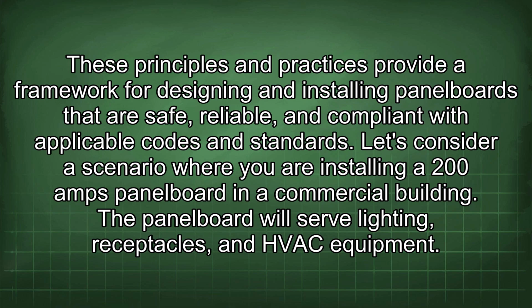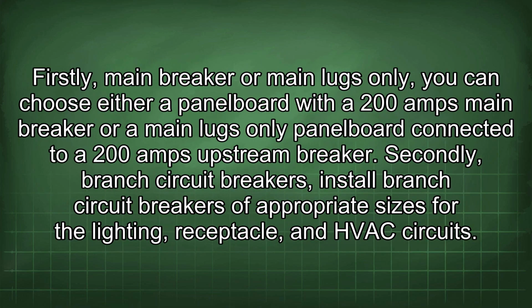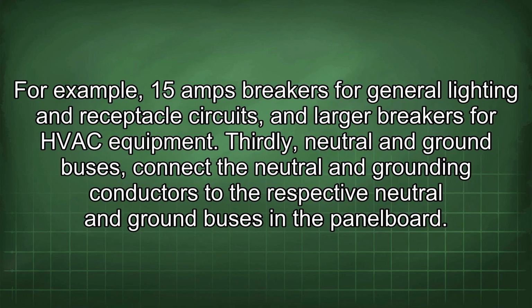The panelboard will serve lighting, receptacles, and HVAC equipment. Firstly, main breaker or main lugs only. You can choose either a panelboard with a 200 amps main breaker or a main lugs only panelboard connected to a 200 amps upstream breaker. Secondly, branch circuit breakers. Install branch circuit breakers of appropriate sizes for the lighting, receptacle, and HVAC circuits. For example, 15 amps breakers for general lighting and receptacle circuits, and larger breakers for HVAC equipment.